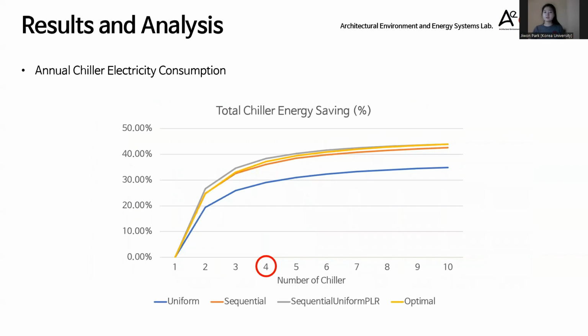The following is an analysis of energy savings compared to case 1. By using 2 chillers instead of 1, there was an annual energy savings of over 20% in cooling energy consumption. Additionally, as the number of chillers increased in all algorithms, the energy savings in cooling also increased gradually. As observed in the graph, the sequential uniform PLR algorithm showed the greatest cooling energy savings.